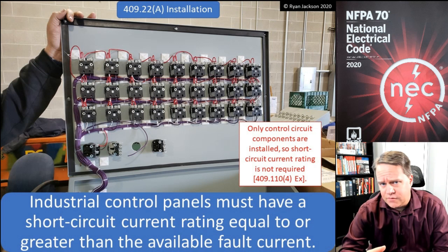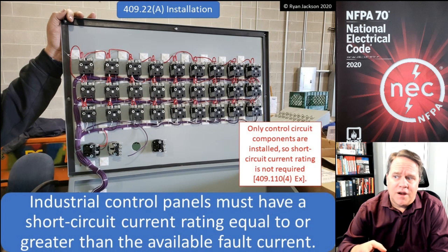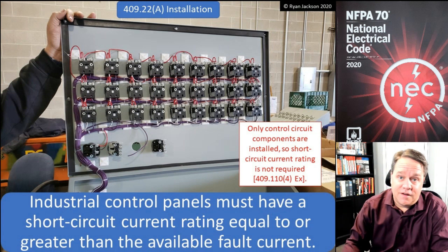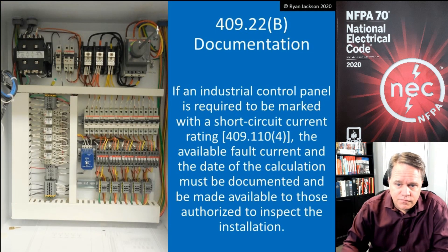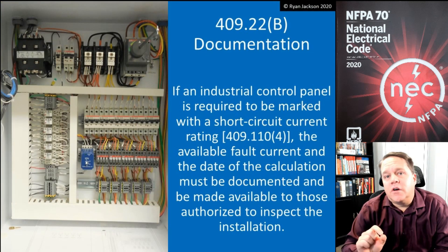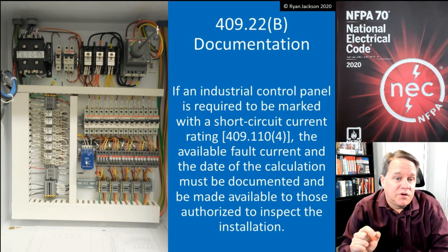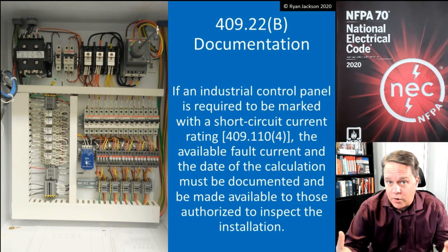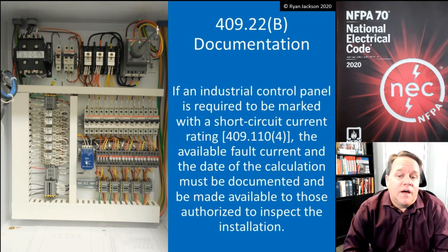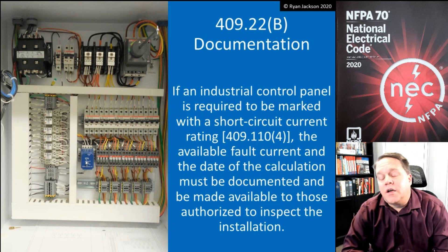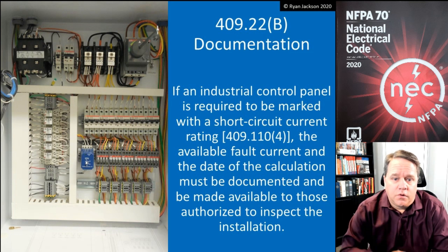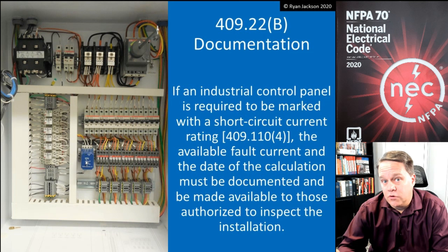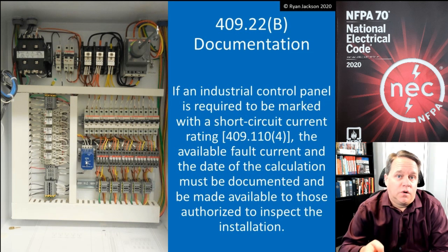Industrial control panels don't have to be listed, but if they have to have a short circuit current rating, that's going to be tough — that's not something you can figure out in the field without a field evaluation. If an industrial control panel is required to be marked with a short circuit current rating, which means there are power components in there, then the available fault current and the date of the calculation must be documented and made available to those authorized to inspect the installation. Looking at this photograph, that panel has power components and control components, so it has to have a short circuit current rating.